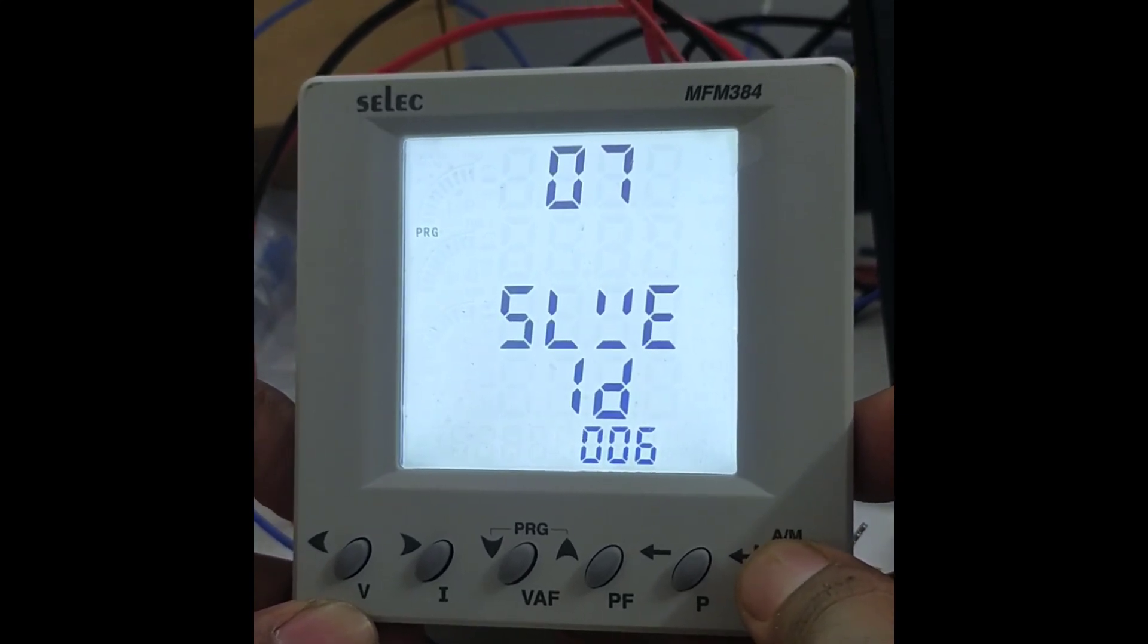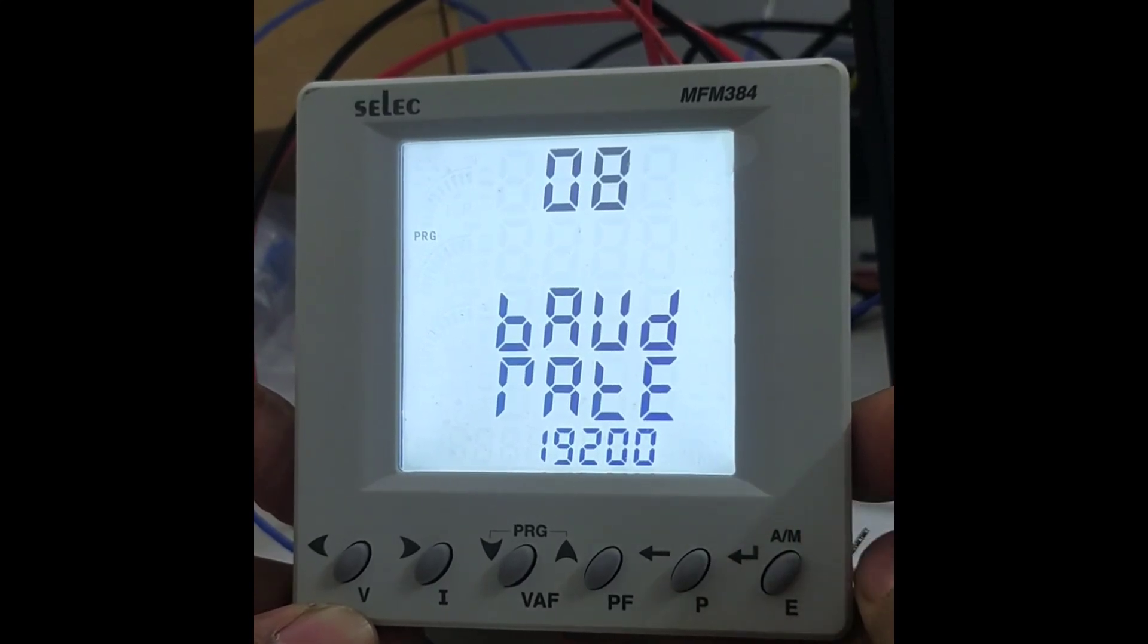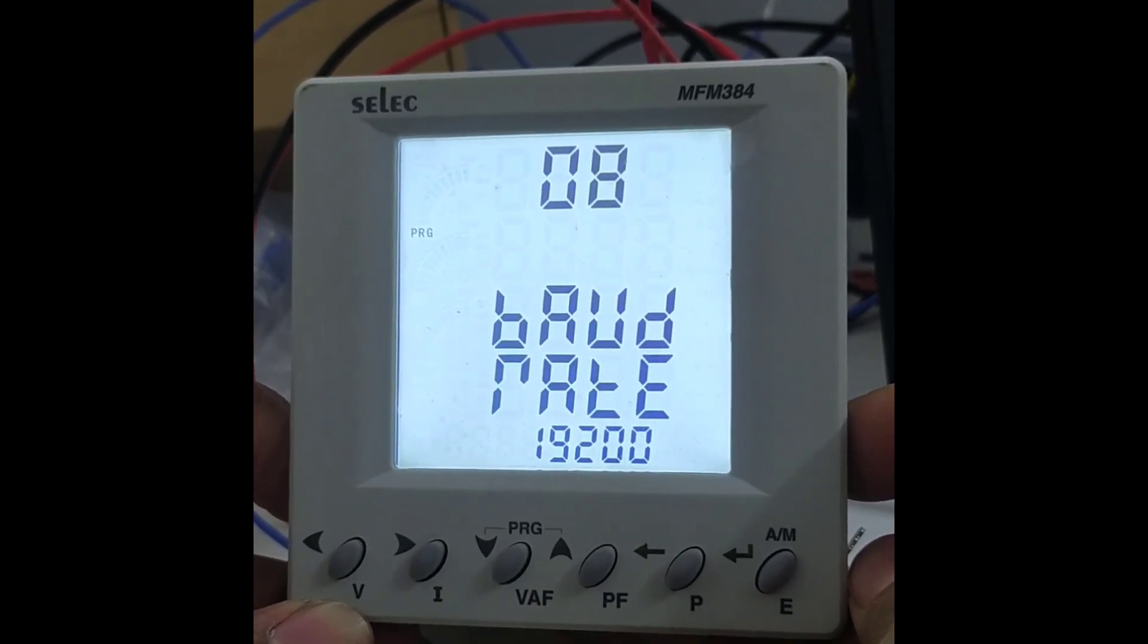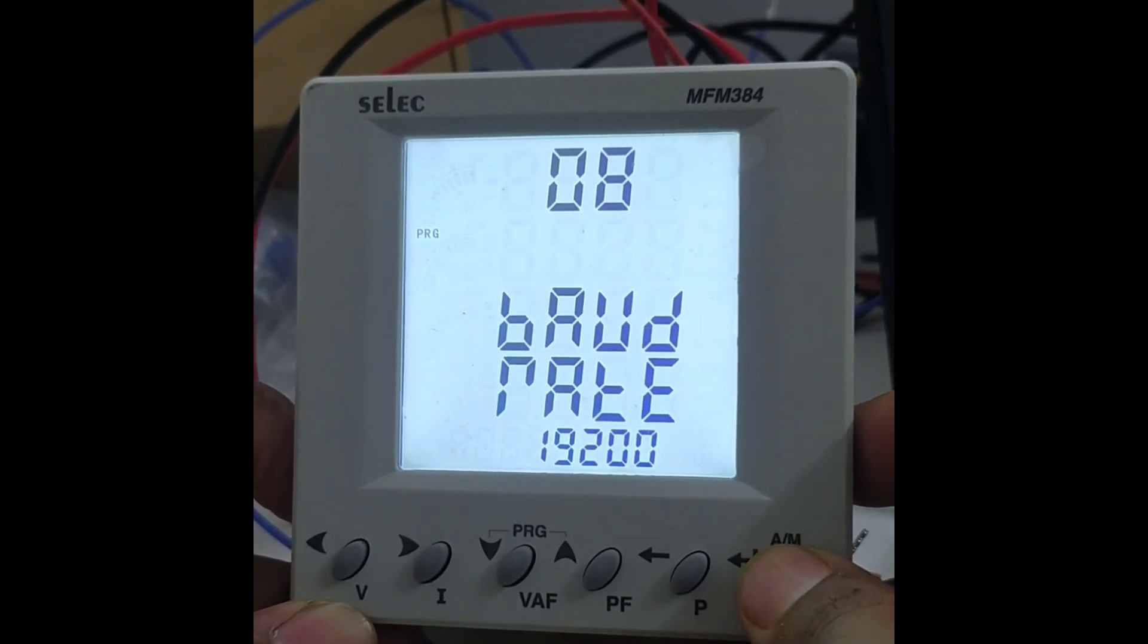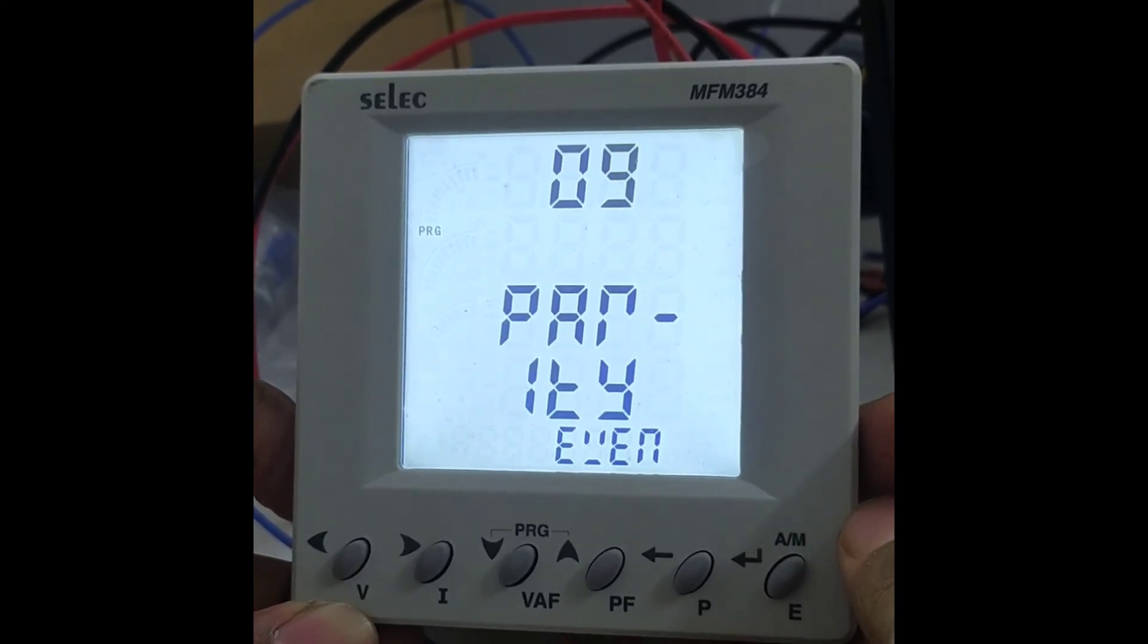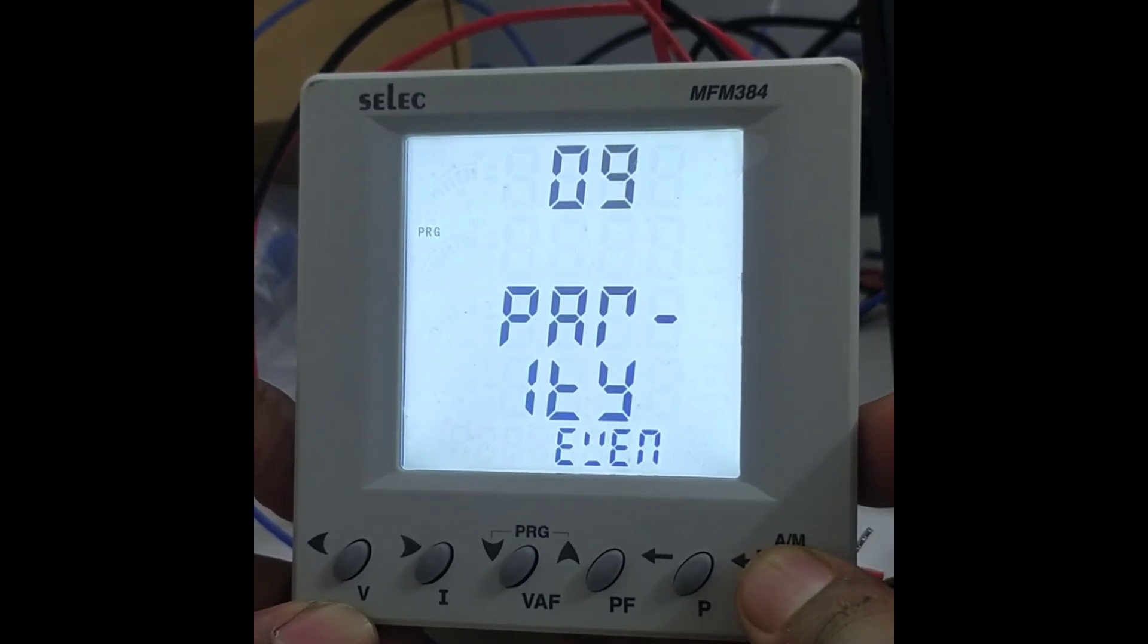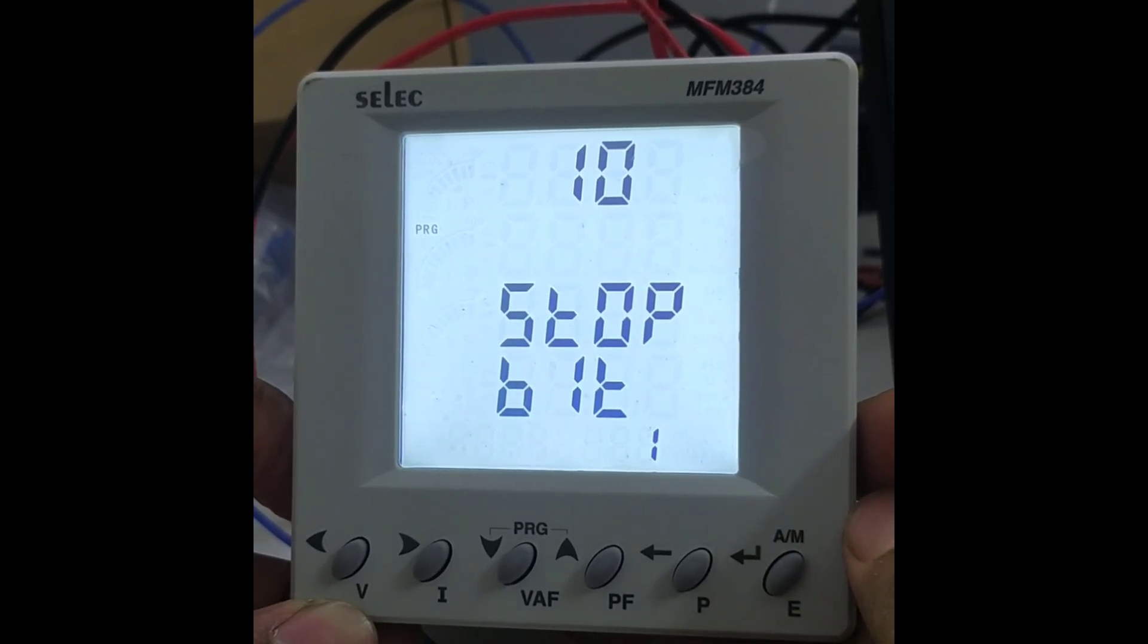Press enter. It's showing the baud rate, which is 19200. The next parameter is parity, which is even. You can change it with the help of the upper and downward buttons. Next, press enter. It's showing the stop bit, which is one.